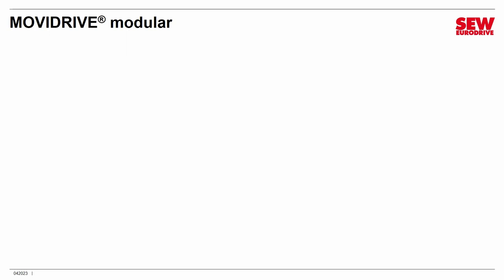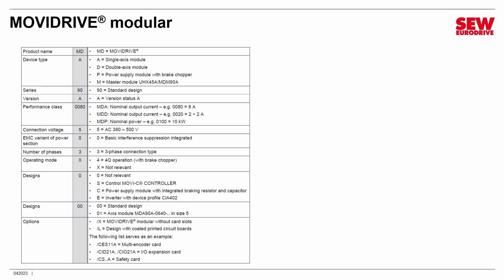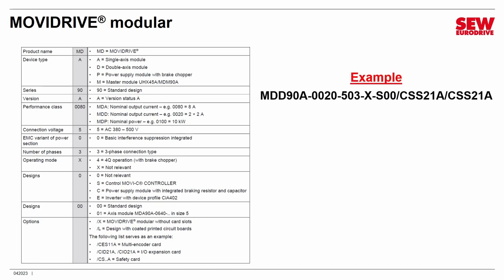Now let's do a MoviDrive Modular example. MoviDrive Modular has multiple pieces, so we need to understand its nomenclature. A sticker reads: MDD 90A-0020-503-X-S00/CSS21A/CSS21A. MD means MoviDrive and D means double-axis module — axis modules are only part of MoviDrive Modular setups. So this is a MoviDrive Modular double-axis module that supports two motors.